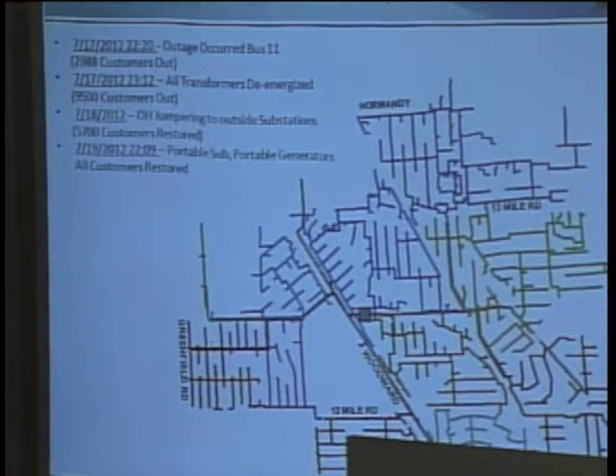The restoration procedure was that the outage occurred on bus 11, so you had 2,988 customers out. Webster substation is a three transformer substation. Each bus is the feed from the transformer to a number of circuit breakers. Those circuit breakers then feed portions of the city of Berkley and Royal Oak. Outlined in the different colors are the circuits out of Webster. And what happened, according to the outage, is when they had the 2,988 customers out, all the transformers had to be de-energized in order to put the fire out.